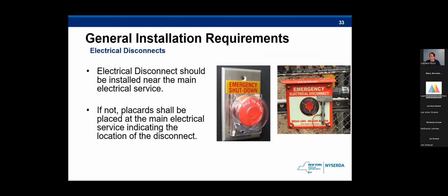So now we're moving into what's called the general installation requirements of the code, and we'll be beginning with the electrical disconnect. Once again, all systems that this code is relevant to must meet all these general installation requirements. For electrical disconnects, these are extremely important, largely to first responders, and they should be in a secure location with signage to direct the fire department to the proper place. Even though you may shut down the energy storage system, the stored energy inside the batteries does not just dissipate. So that is a key point to be aware of. This one device can shut down all cabinets or containers that are at the site. So firefighters should be advised to be careful when shutting down the system when there are no signs of fire.